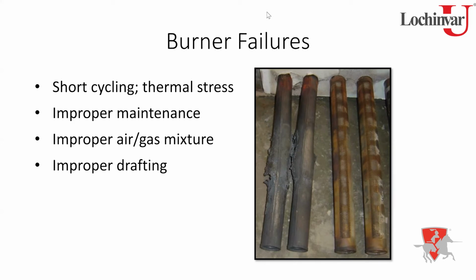Now, something else that could cause a burner failure, though I hope you would never do this, would be if you installed the burners in upside down, as you see in this picture. This did actually happen. You've got to try really hard to do this because the screw holes will not line up, so you do have to put in additional screw holes to make self-tappers. Unfortunately, that's what happened in this scenario. So, yeah, please don't install your burners upside down.